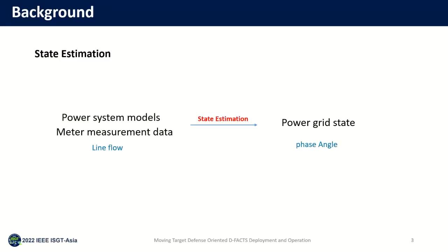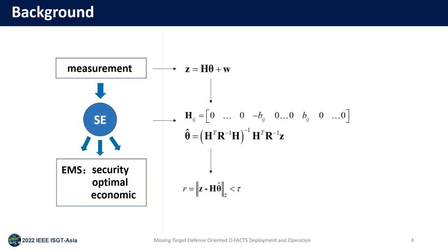In the process of power system operation, state estimation plays a key role. The system state is estimated from the system measurements and the system model. In the DC model, the measurement value is the line flow represented by vector Z, and the state is the bus phase angle represented by vector theta. In the relationship between the measurement value and the system state, matrix H consists of the line reactances. System state can be obtained by least squares estimation.